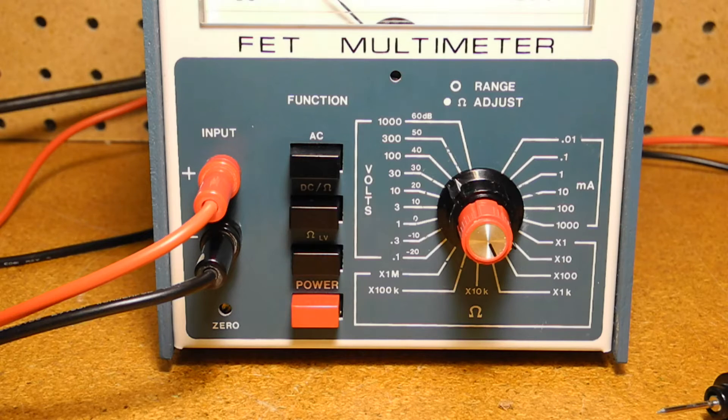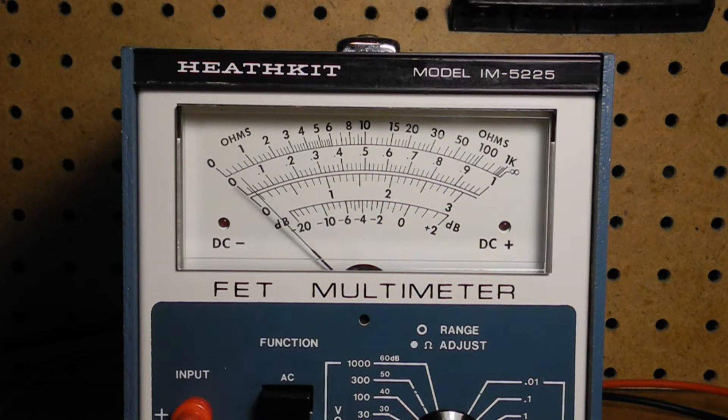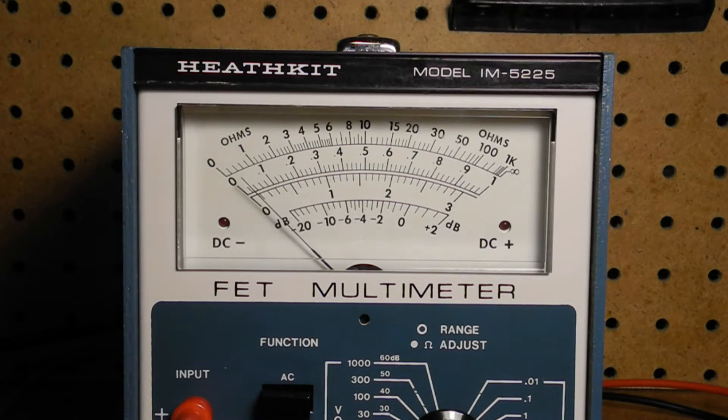AC volts supports the same nine ranges with an accuracy of plus or minus 3% for 60 Hz sine waves. It responds to the average value of the rectified waveform and is calibrated in RMS voltage. Input impedance is 10 megaohms with about 100 pF input capacitance. The frequency response is 10 Hz to 100 kHz, going down to 50 kHz on the 1000 volt range. It also has a scale for showing AC voltages in decibels based on 0 dB being 1 milliwatt across 600 ohms.